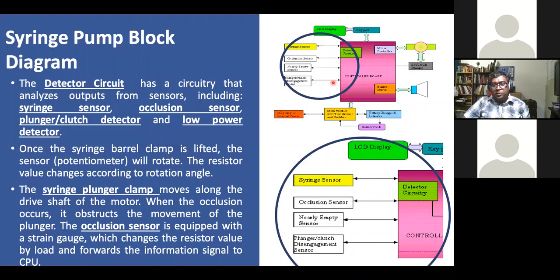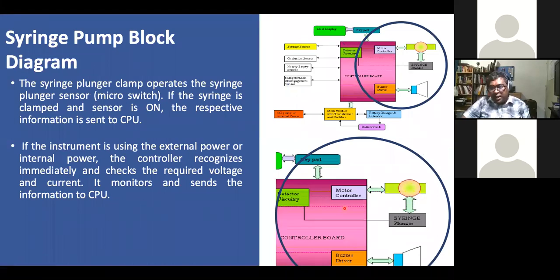So the syringe plunger moves along the driver shaft and motor. When there's an occlusion or obstruction of movement, the occlusion sensor will indicate a certain pressure and will give information to the control board. So all the movement of the mechanism is monitored. Any change of pressure on the line will be monitored. These are the key sensors monitoring all this, and it's a patient safety function actually. On the other end, you can see the alarm and the syringe plunger movement, all that.